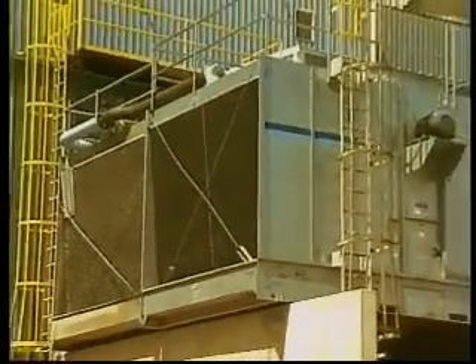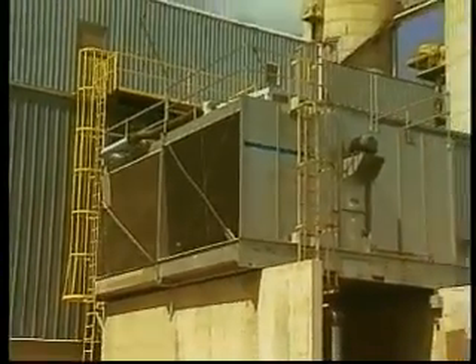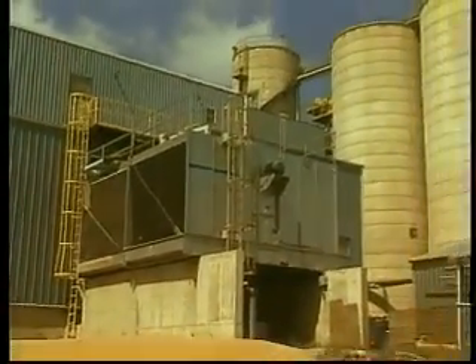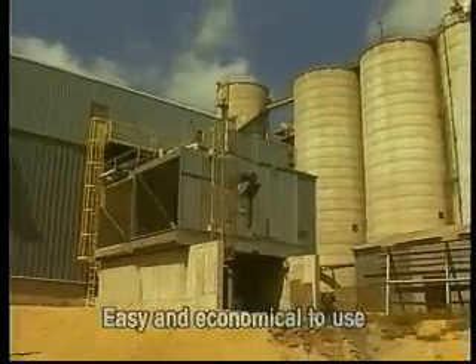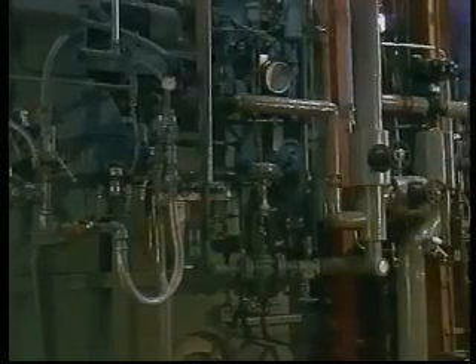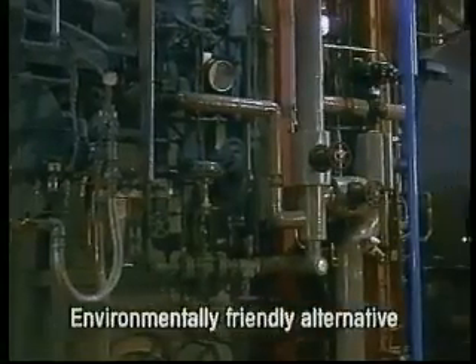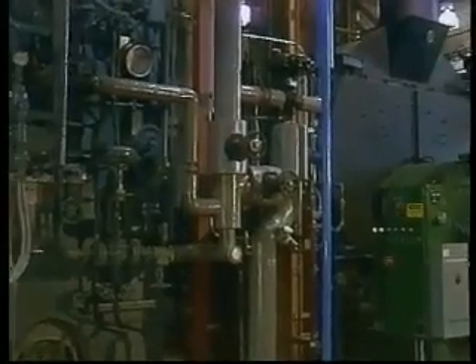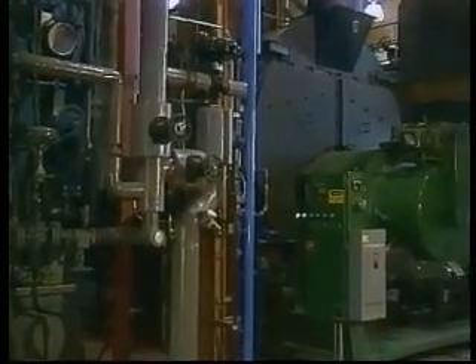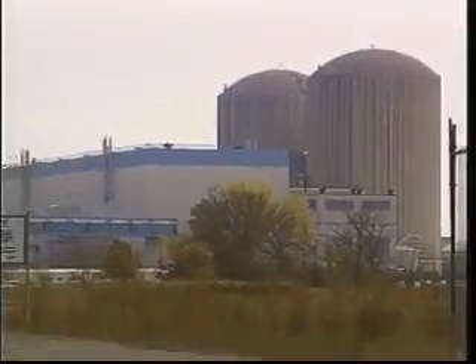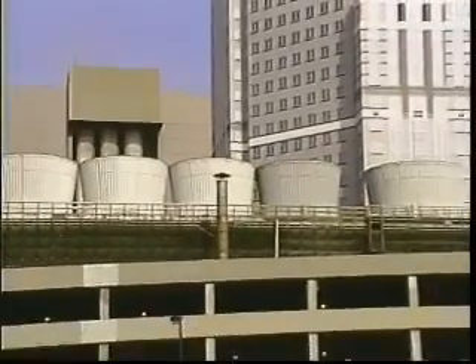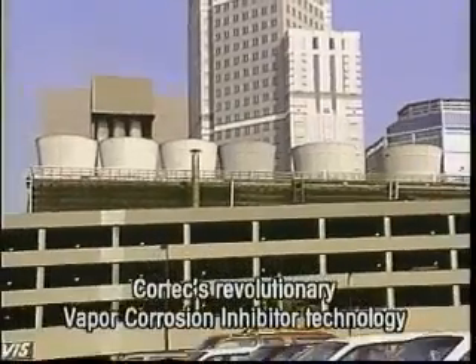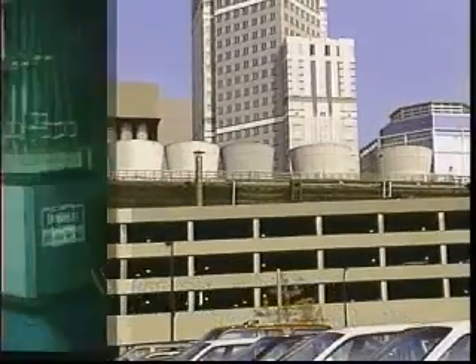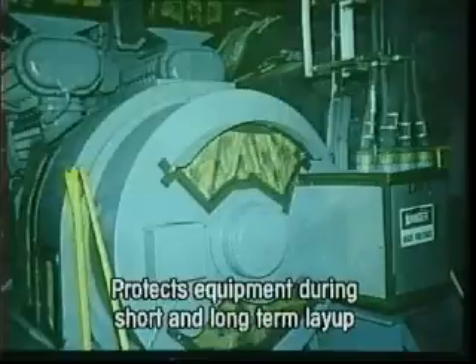Cortec corrosion inhibitors offer significant advantages over traditional layup methods. Not only are they easy and economical to use, but also an environmentally friendly alternative to other corrosion protection methods. Cortec boiler lizards, cooling loop gators, closed loop toads, cooling tower frogs, and VpCI 649 use revolutionary vapor corrosion inhibitor technology to protect equipment during short and long-term layup.